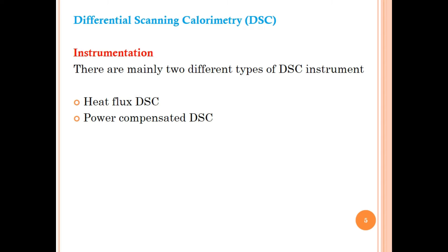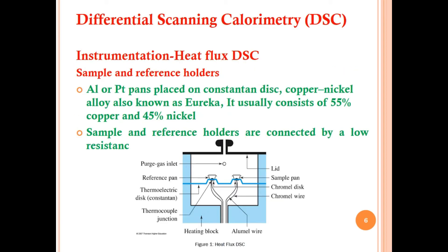Let us discuss the instrumentation of DSC. There are mainly two different types of DSC instruments: heat flux DSC and power compensated DSC. This is a block diagram for DSC — heat flux DSC — showing sample and reference holders, which are parts of the heat flux DSC instrument.